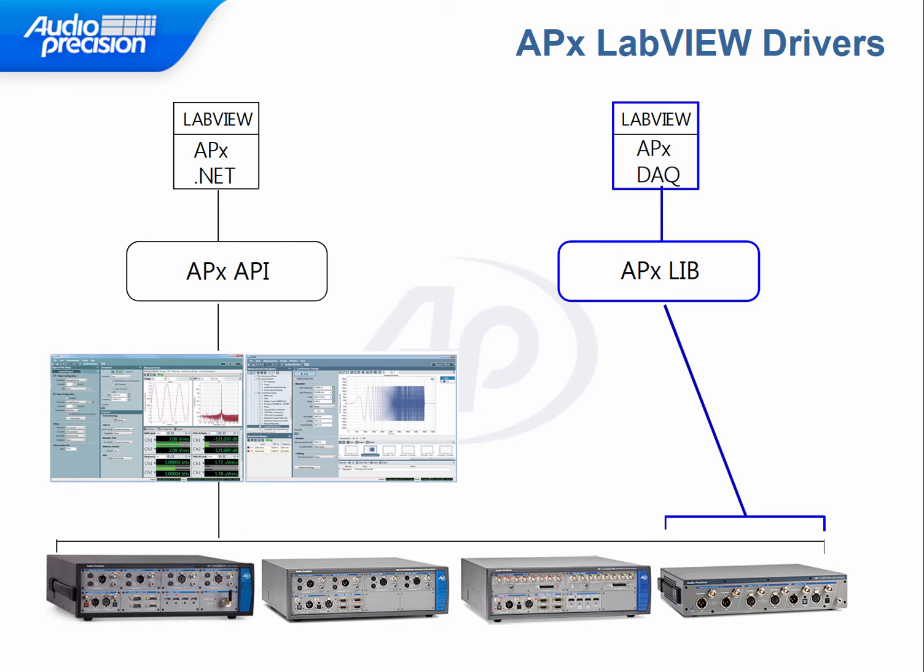Secondly, we have the APx LabVIEW DAQ Driver. This is more of a typical LabVIEW data acquisition driver. It uses a low-level C++ library that controls the interface to the analyzer, and it only works with the APx515 audio analyzer, which is intended for production test.